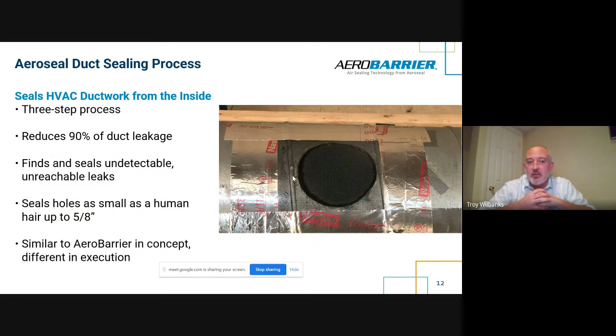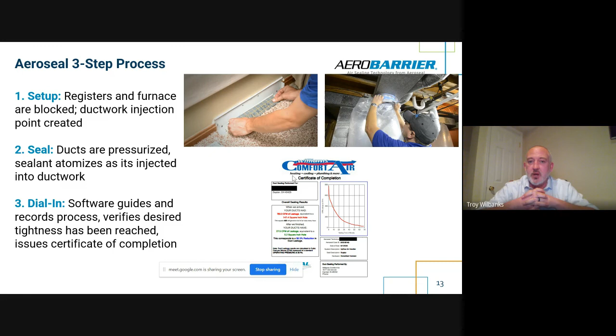The first thing our crews do is set up—they block the registers and furnaces, and put injection points in the ductwork. The sealant is atomized and pressurized, then goes through and finds those leak points, sealing them up from the inside out. So no more ripping out drywall, no more wondering if you're going to pass a duct blaster test. It also increases the efficiency of the specified or existing equipment if you're keeping it for a rehab. Then you get your certificate right there, which, depending on the municipality, can be used as proof of compliance for a duct blaster test.